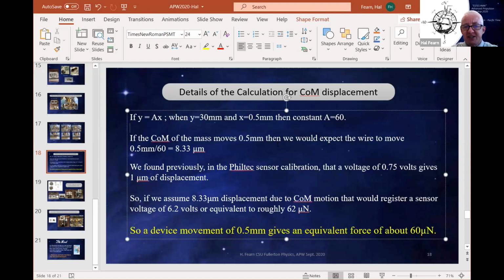So let's say the center of mass of our device moves by 0.5 millimeter. Then you'd expect the wire to move by 0.5 millimeter divided by 60, which is about 8.3 microns. We previously saw the Philtec sensor calibration, where I got 0.75 volts gives a micrometer displacement. So 8.33 microns would give a sensor voltage of about 6.2 volts, and that's roughly equivalent to 62 micronewtons. So what I found was that if the device moves 0.5 millimeters, you get an equivalent force of about 60 micronewtons. The thing is, the forces that we're seeing now are way, way bigger than 60 micronewtons.